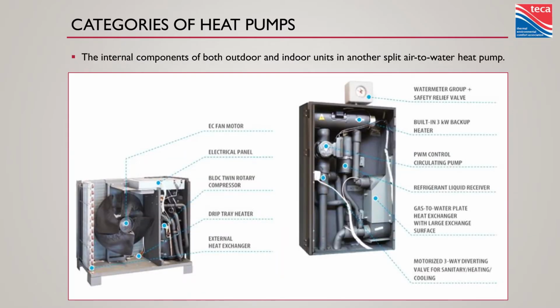Now, typical components in these things, we have a fan on the outdoor unit that's going to move that air across that heat exchanger. We have the heat exchanger itself, the compressor. Most of the refrigeration components are going to be in the outdoor section in these split heat pumps. In the indoor unit, you've got the other heat exchanger, refrigerant to water, sometimes a circulator pump, sometimes some electric elements for auxiliary heating. Flow switch, almost always, because proving flow is essential before we run that compressor. And other typical safeties we would think of, relief valves, auto vents, those kind of things in any kind of heat source.